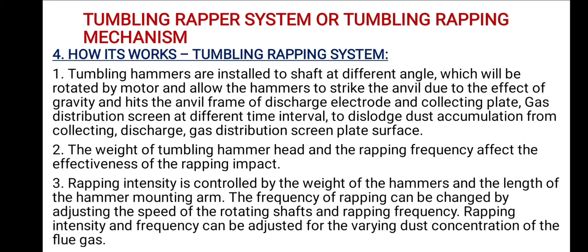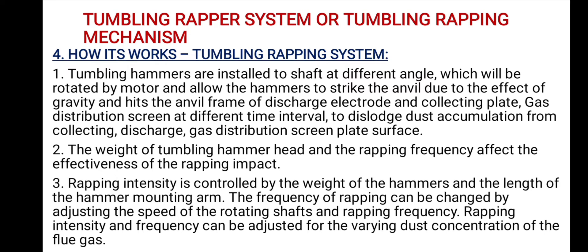The weight of the tumbling hammer head and the rapping frequency affect the effectiveness of the rapping impact. Wrapping intensity is controlled by the weight of the hammers and the length of the hammer mounting arm. The frequency of rapping can be changed by adjusting the speed of the rotating shafts. Wrapping intensity and frequency can be adjusted for the varying dust concentration of the flue gas.